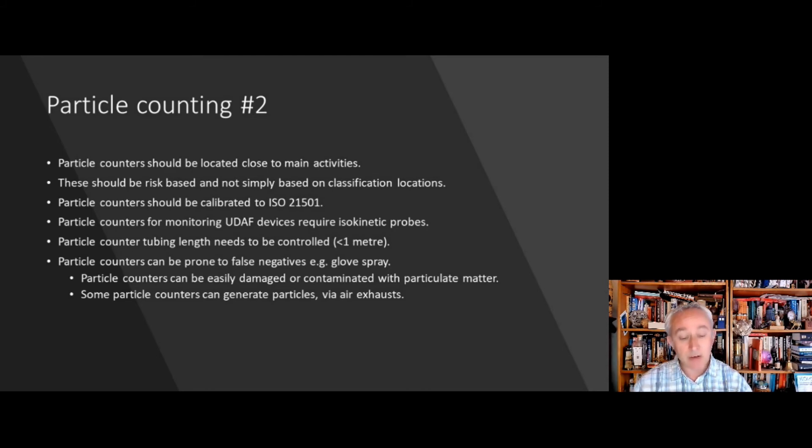We also need to understand the conditions and the way people operate because particle counters can sometimes be prone to false negatives from spraying of gloves. We want to have our glove spray station away from where we're situating the particle counter, and we need to be careful not to damage the particle counter because they can easily be contaminated with things like glove spray and other sorts of particulate matter.